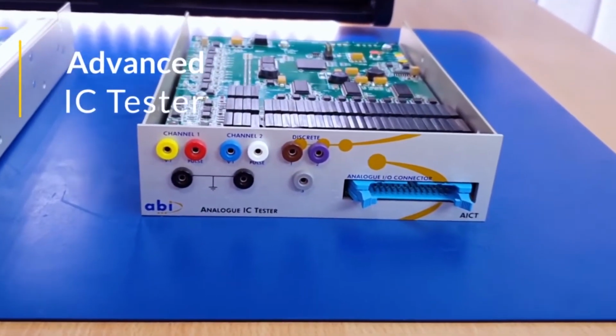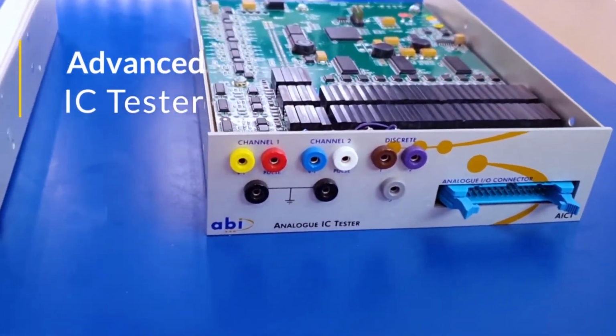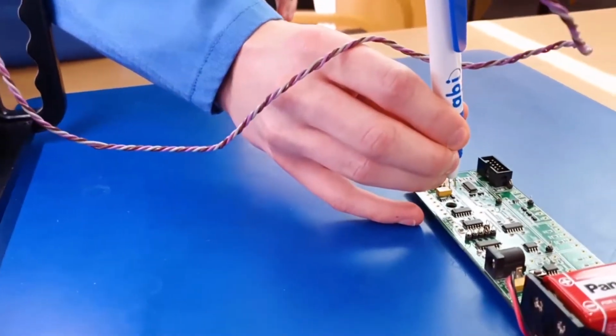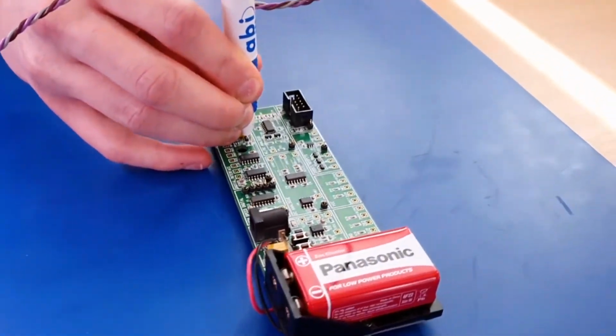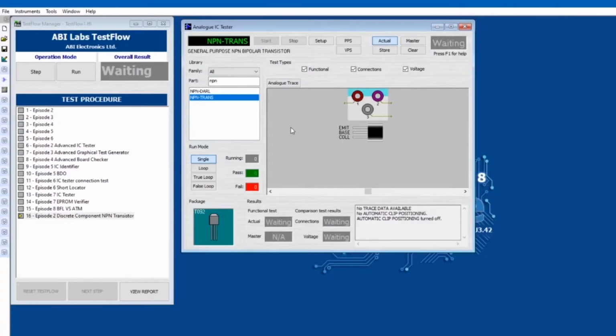Sure, so with the AICT we have 2 channels for VI and 3 channels for discrete. We also have the 24 pins available with the analog I/O connector, which can be used to test analog ICs in circuit. Right, okay, great.